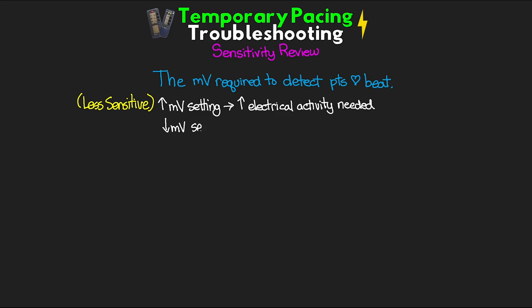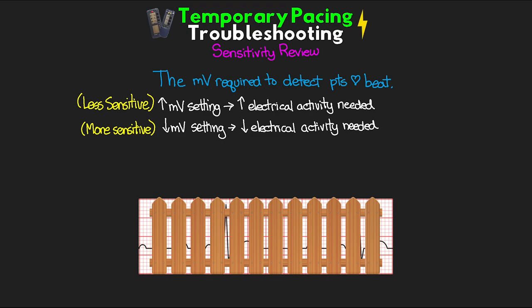On the flip side, the lower the millivolt setting, the less electrical activity it takes to be detected as a heartbeat — making the pacemaker more sensitive. It's helpful to think of this like a fence: the fence is our millivolt setting, and underneath is the patient's intrinsic heart rhythm. The higher you are on the paper, the greater the millivolt of electrical activity. The higher the fence, the less sensitive we are to the underlying activity; the lower the fence, the more sensitive we are.